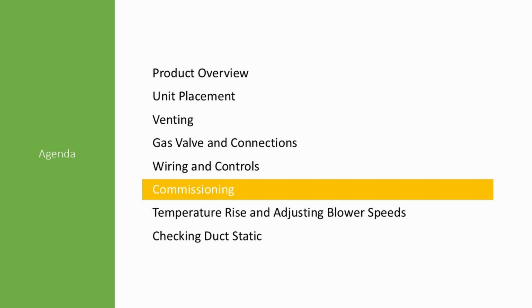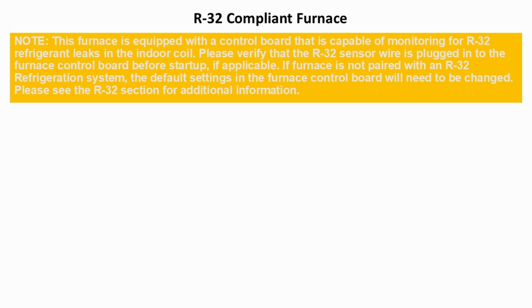Commissioning. R32 compliant furnace. Note: the furnace is equipped with a control board that is capable of monitoring for R32 refrigerant leaks in the indoor coil. Please verify that the R32 sensor wire is plugged into the furnace control board before startup, if applicable. If the furnace is not paired with an R32 refrigerant system, the default settings of the furnace control board will need to be changed. Please see the R32 section in the installation manual for additional information.